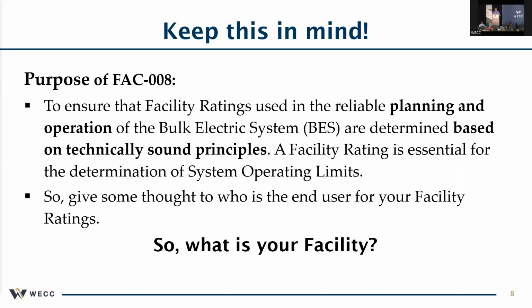So understand, we looked at FAC 8, and there is nothing in FAC 8. There's two things 881 is going to require you to do. It's going to require you to do ambient adjusted ratings for your facilities. And this order, by the way, is directed for open access tariff. It's not a reliability standard type rating. It's not directed towards reliability standards itself. But the TOs that determine these ratings, FAC 8 is their tool that they do that for. We don't think FAC 8, as it is right now, prohibits incorporating all the requirements for 881.